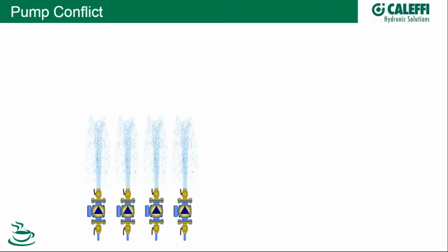And I have them in an open system here. The size of the water column squirting up out of the pumps is really to indicate the flow rate in each of these 4 circulators. What we want to have happen is that when one pump turns off, of any of these 4, it doesn't increase the flow rate in the remaining open pumps. And then when the pump that turned off turns back on, we don't want it to suppress them. This would be an example of decoupled circulators in a system.